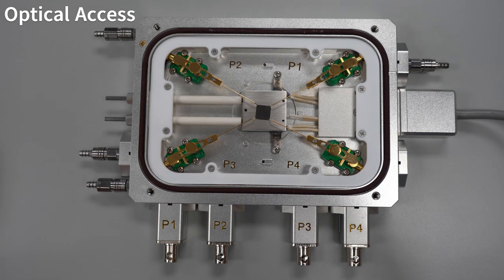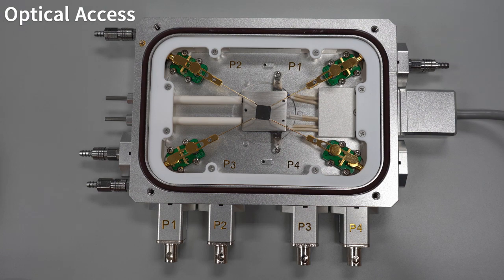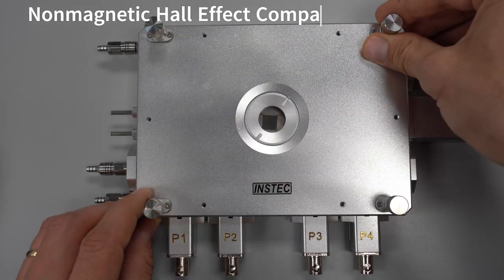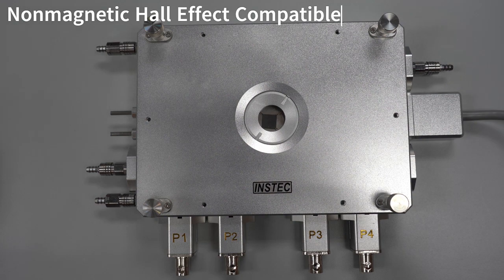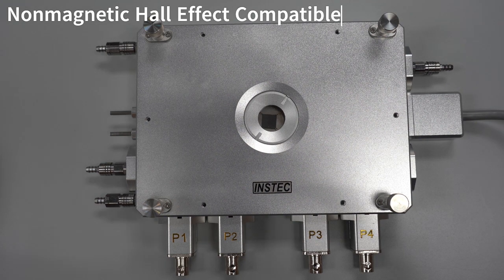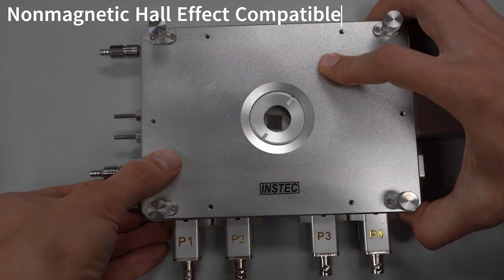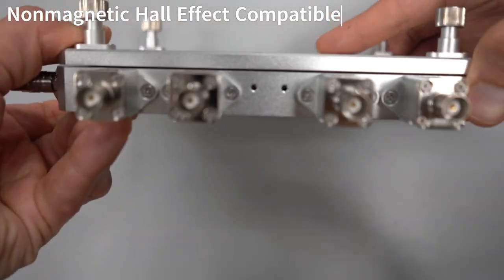This is similar to the P02S-PM, but adds the benefit of thermal control as well as environmental control with a large optical access window. It can also be made using totally non-magnetic materials for use in our Hall Effect measurement systems, and has a low footprint for fitting between magnetic poles or optical microscopes.